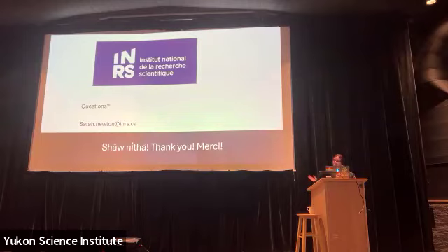I have colleagues working on northern communities all across the country. One is working in Northwest Territories, and his modeling expected that you'd need to put more distance between the boreholes to reduce what they call thermal interference. That's really important. When you put those parameters into a ground heat exchange software, there are programs that run the calculations needed to size these systems, taking into account the distance between boreholes and the size of the bore field.